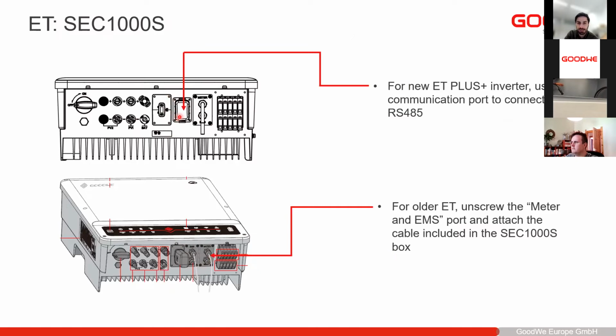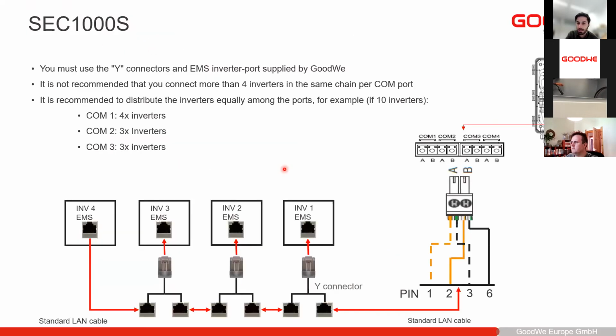Then you instead have this big connection here in case you want to use a SEC1000S. And this is what I showed you with the white connection that goes in here. And then you have this spare cable that I showed, and you have a splitter, and you can connect up to 4 inverters in daisy chain. And then you get this thing with the SEC1000S, and then you just connect it to one of the comms.